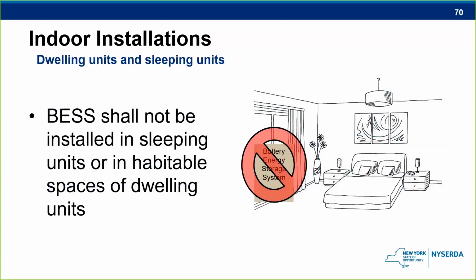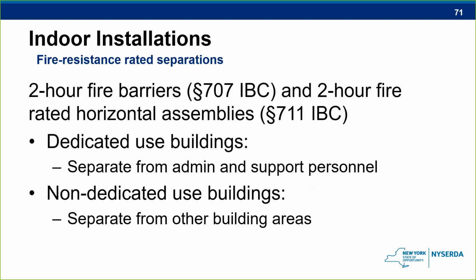Okay, so otherwise, the additional indoor requirements are that the energy storage system cannot be installed inside of a dwelling location. When an energy storage system fails, it may release toxic fumes that could be really bad for a human, possibly even kill them. And for those reasons alone, the risk is too great, so don't install them in sleeping units or habitable spaces. For any of them, 2-hour fire barriers are needed in a room or area. This includes the ceiling as well as the walls.